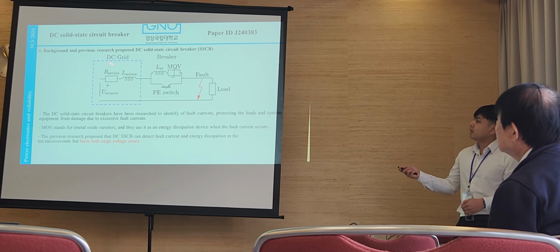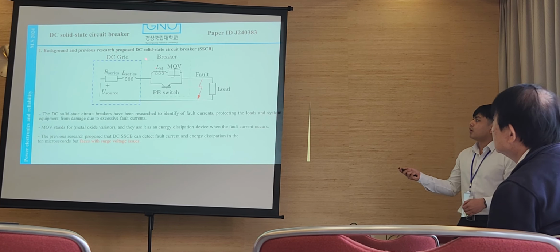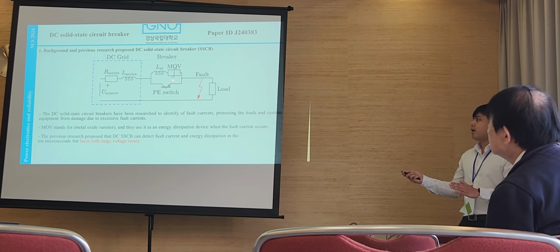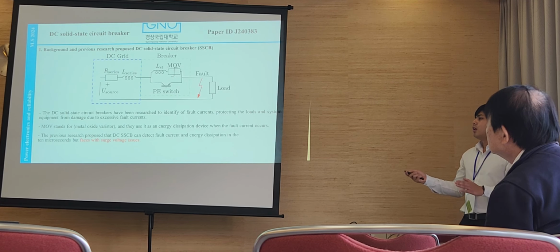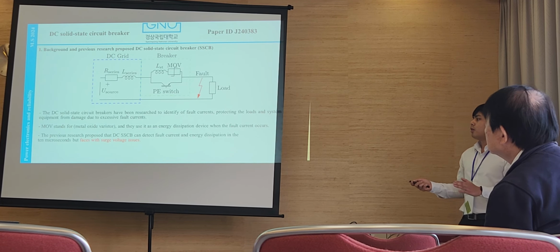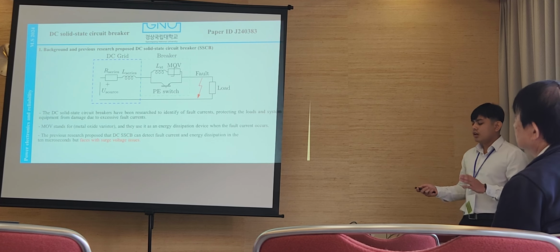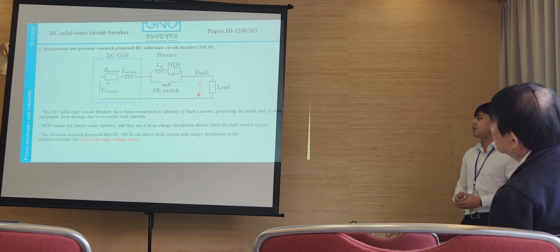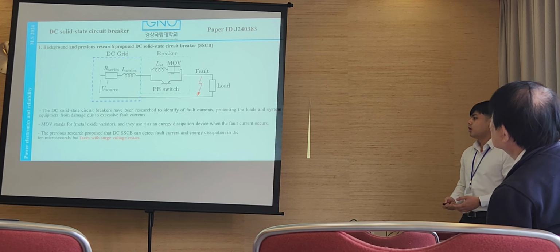You can see in the circuit, they divide into DC grid and breaker. In the breaker path, you might see a MOV device. MOV stands for metal oxide varistor, and it acts as the energy dissipation device when the fault current occurs.